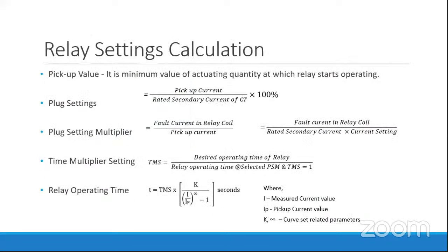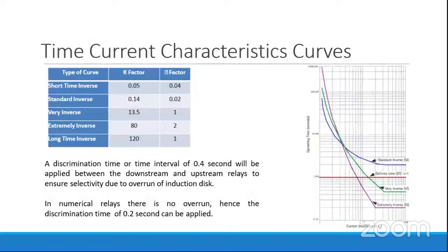With these values we can set certain parameters in the relay, and accordingly the relay will measure the current values, and if they go beyond the threshold value, the relay will start to trigger. The relay will trigger and operate at a certain time period. This time period can be known with the time current characteristics curve, the TCC.